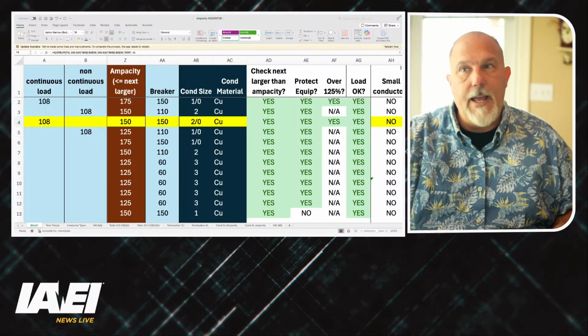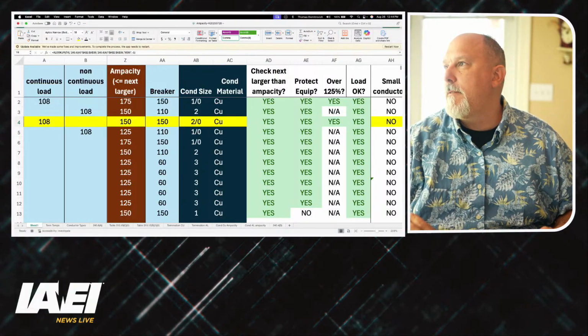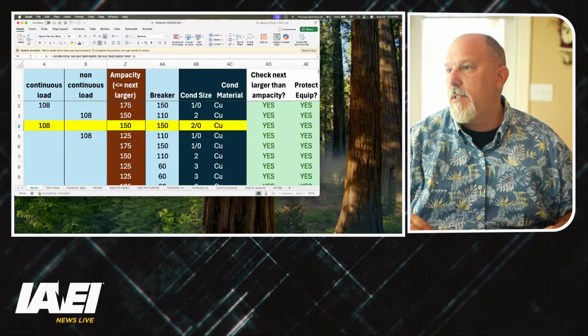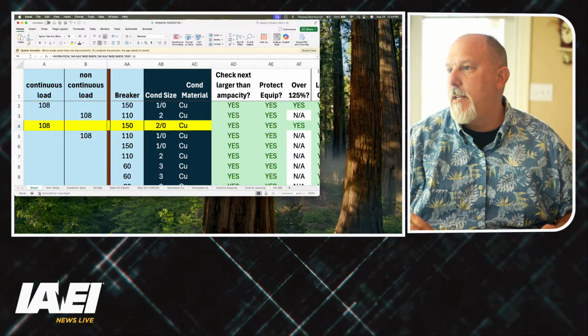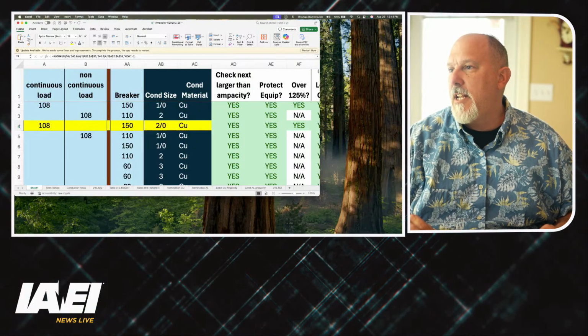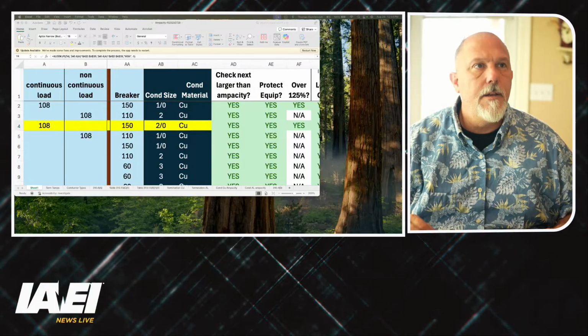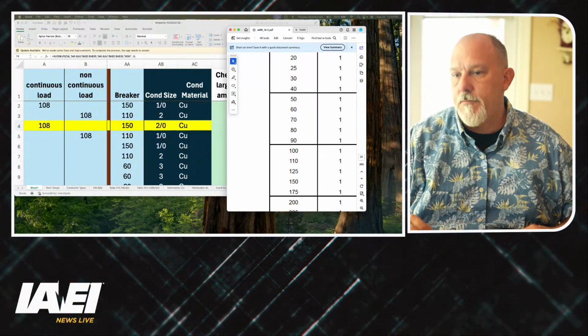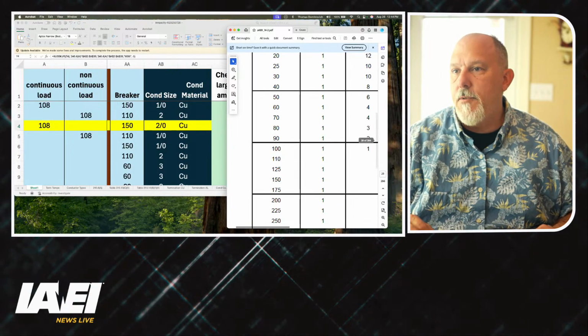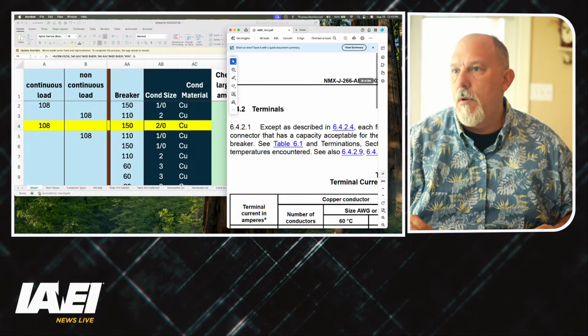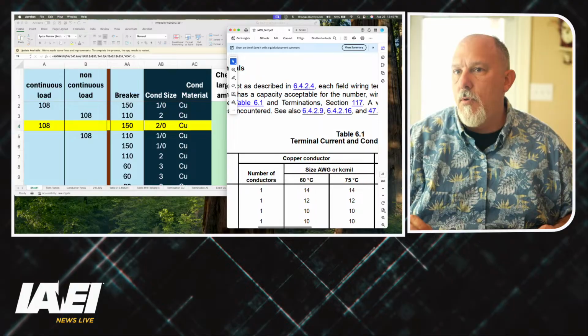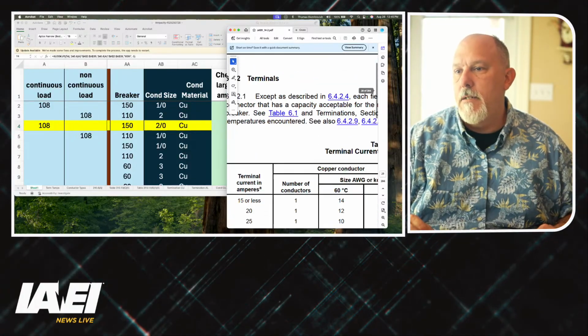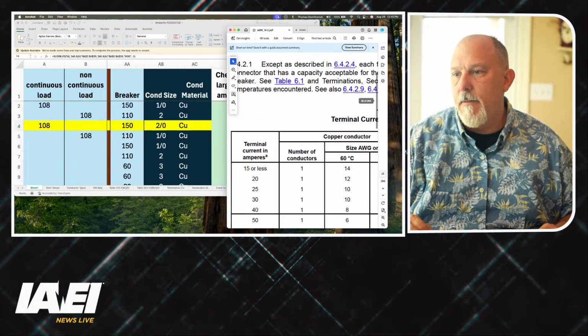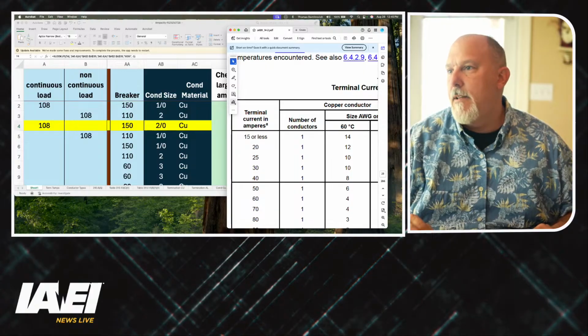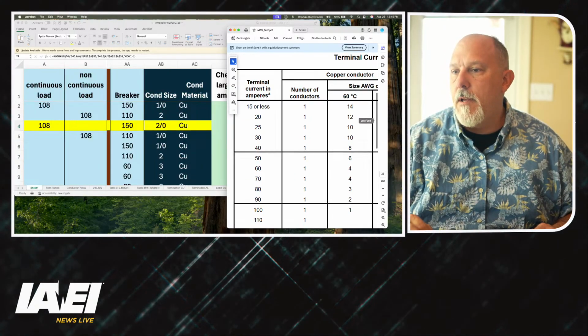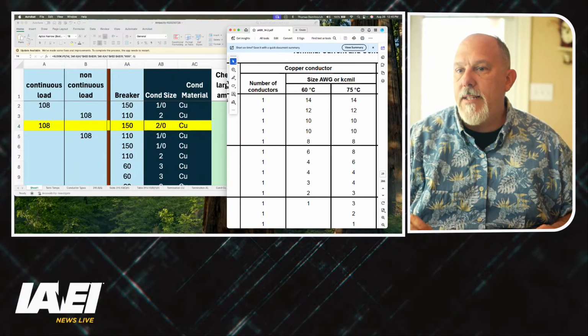So what we've got here: a 150 amp breaker with a 2/0, a 110 amp breaker with a 1/0, a 110 amp breaker with a number 2. Let's bring this table over. This is in UL 489, and this is Table 6.1. I need 150 and 110 amp. There's 110 amp, and we test that with a number 2.